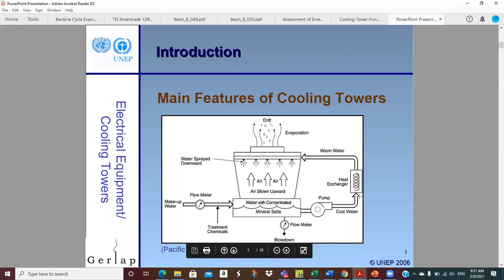So we're going to pump up through there. This would be our condenser water pump. If it's a chiller, pump through the condenser with a heat load. So typical number, come in at 85, come out at 95. And we go up to the top of the tower where there are distribution basins. And so basically that water spreads out all the way around this. And that basin will probably have a depth of 4 to 6 inches of water. Of course, different types of towers may be configured a little bit differently. And the idea is we want to distribute that water, and there's some kind of nozzles, some sort of spray system here to distribute that.